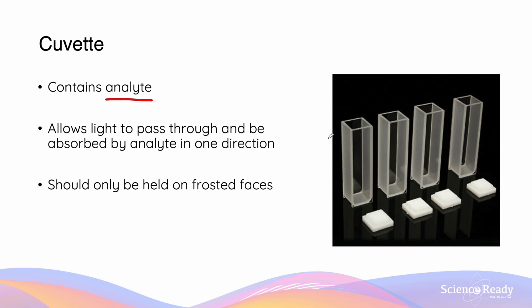The primary reason for being transparent is because they are going to allow light to pass through and be absorbed by the analyte in one direction — through the clear faces. We see that the other two faces are frosted, and the reason for this is to prevent the light from escaping. Also, since the light cannot pass through the frosted faces, it is important that when we handle the cuvettes, we only hold them by their frosted faces. If we get our fingerprints onto the transparent faces, they may produce some unwanted absorption values.